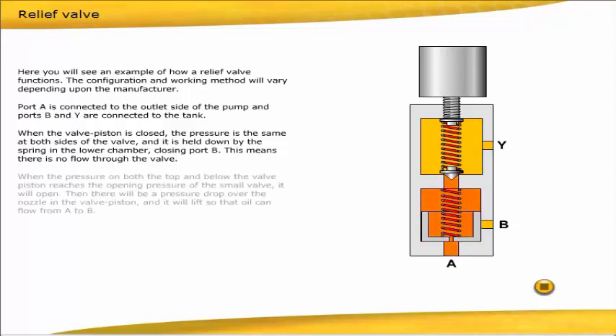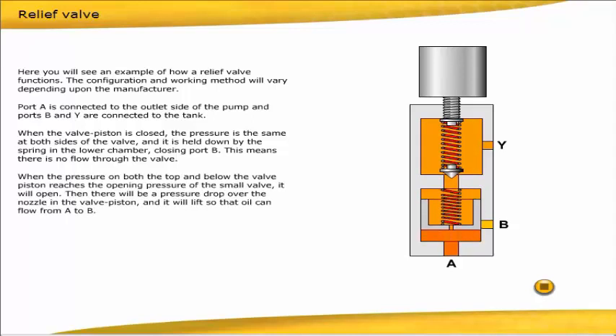When the pressure on both the top and below the valve piston reaches the opening pressure of the small valve, it will open. Then there will be a pressure drop over the nozzle in the valve piston and it will lift so that oil can flow from A to B.